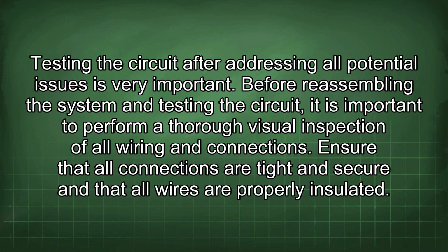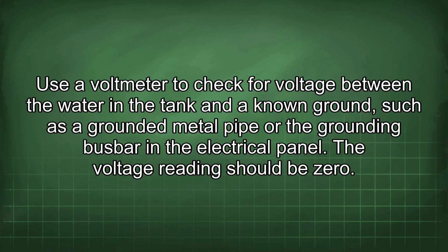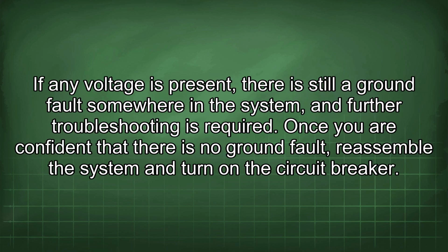Ensure that all connections are tight and secure and that all wires are properly insulated. Use a voltmeter to check for voltage between the water in the tank and a known ground, such as a grounded metal pipe or the grounding busbar in the electrical panel. The voltage reading should be 0. If any voltage is present, there is still a ground fault somewhere in the system, and further troubleshooting is required. Once you are confident that there is no ground fault, reassemble the system and turn on the circuit breaker.